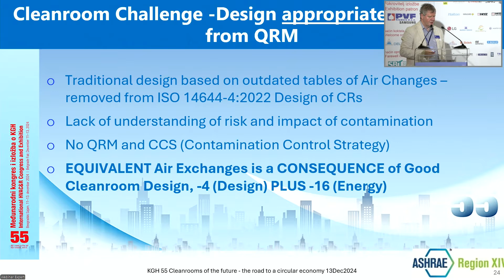And within that good science, we've got to look at local air and how air is moved. Hopefully we'll have time at the end of this to give you an example of airflow visualization in a facility that I've recently worked on for Novartis in Slovenia, actually, last year, where we redesigned the HVAC systems and focused on the efficiency of the system locally to provide containment and removal to give a better product while not conflicting with the compliance requirements on it.